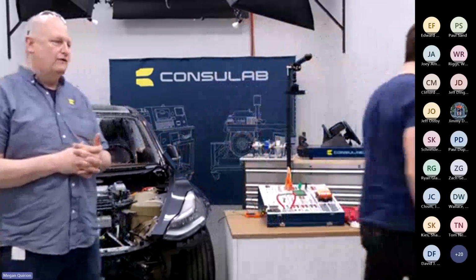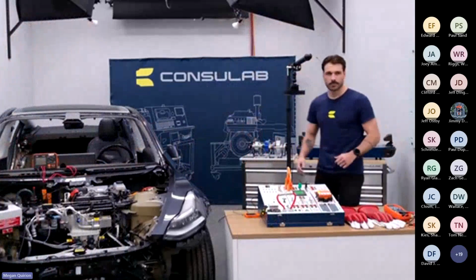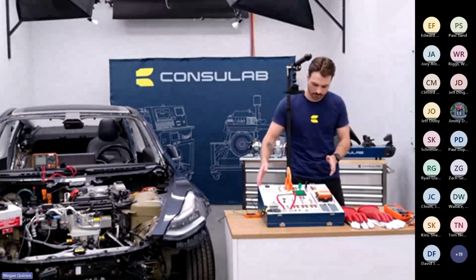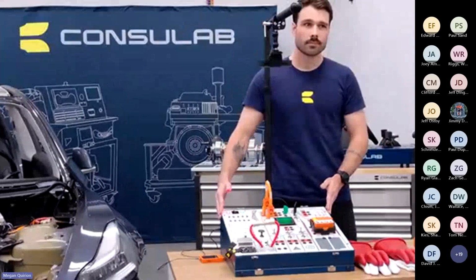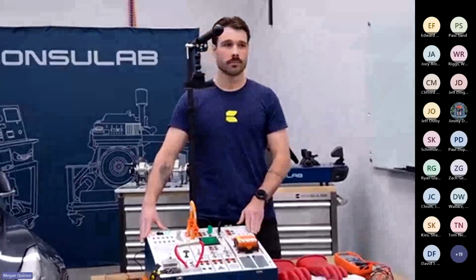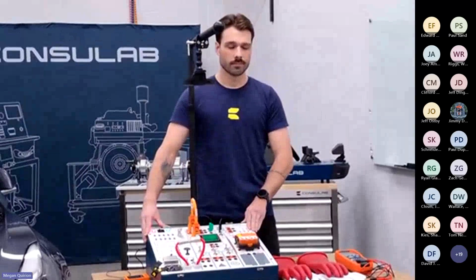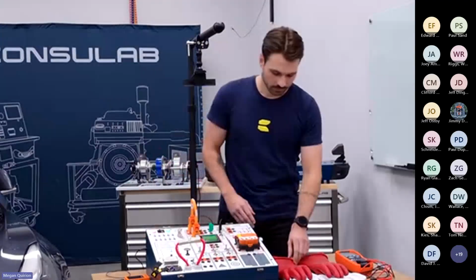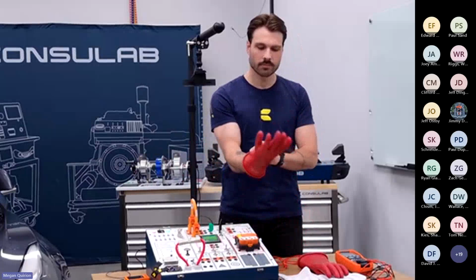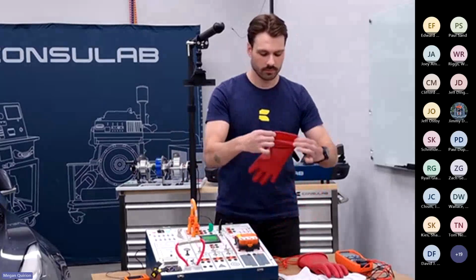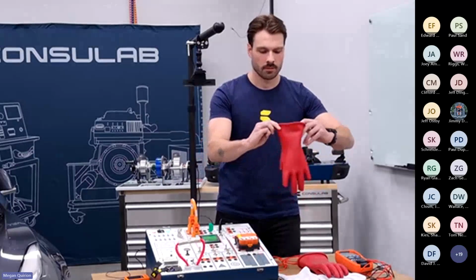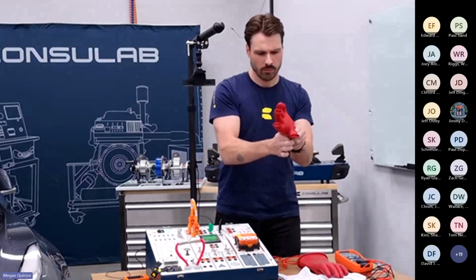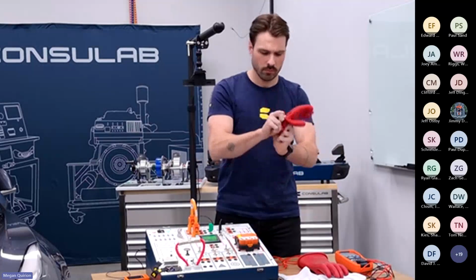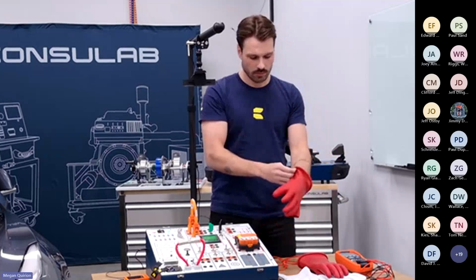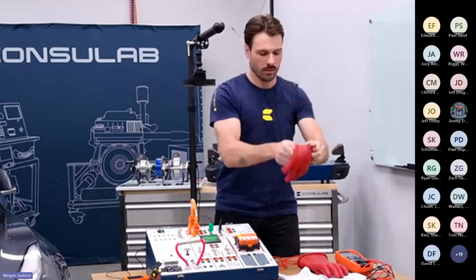So what I'm going to do is get Jerome to go over to our EV 400. This is one of our high voltage trainers that we use for training on high voltage systems. The beauty of this one is it is 400 volts. So the 400 volts is live on this unit. I'm going to get Jerome to put on the gloves. Now, these are class 0 gloves. Obviously, before we use any gloves, we want to field test the gloves to make sure that there are no leaks or cracks.